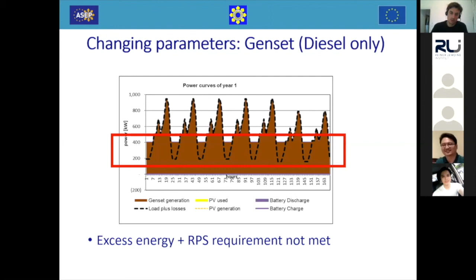And meanwhile, I can explain what will happen. So when you go again to the power flows in your simulation result, you will see that now all the load is covered by the generator. So it is the brown area. But also you see that, for example, in the night, that's when the load is very low, you still have a genset generation because the generator can't go below 30% of its rated capacity.